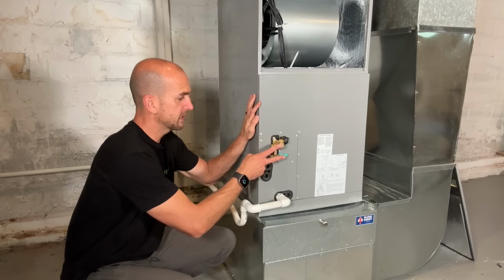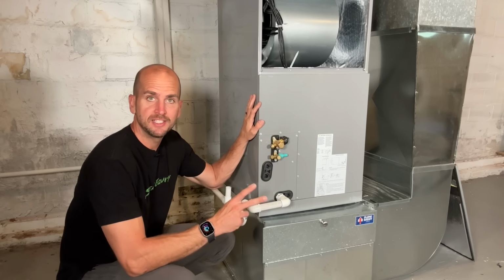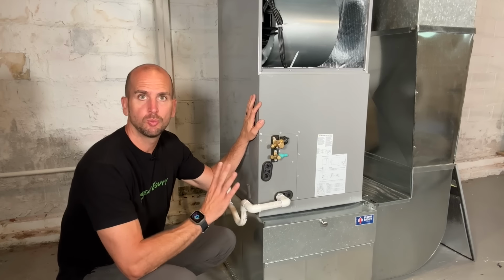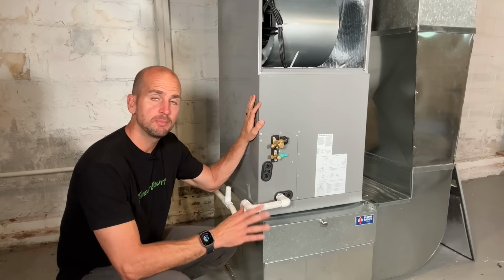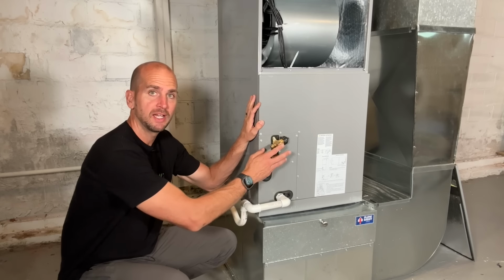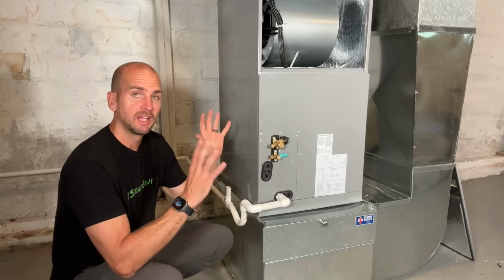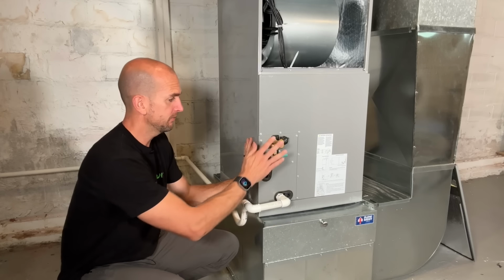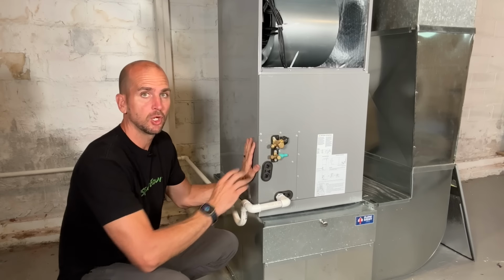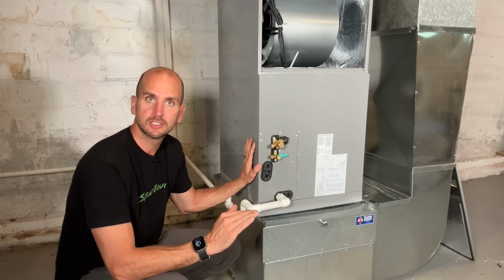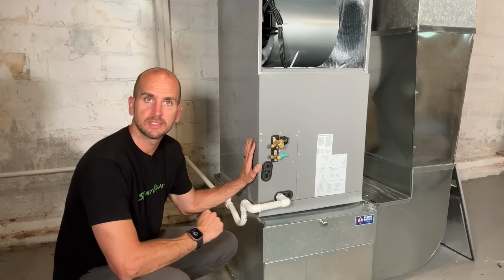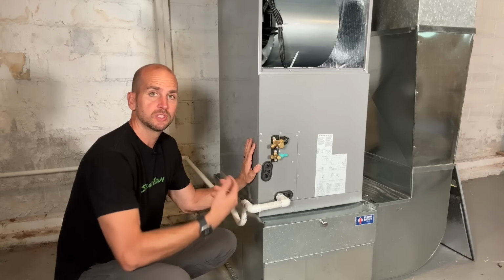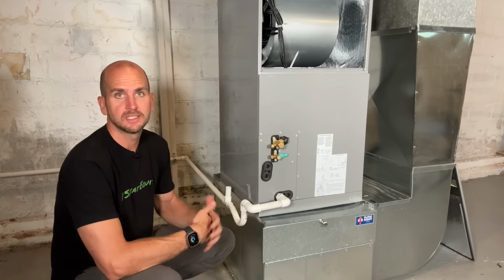So next up, we'll be connecting the No-Vac line set. And this is really the key part to what makes this DIY friendly, because we don't have to install our lines and then pull a vacuum. The line set is all ready to go. If you connect it correctly, you should be able to open up those valves and then everything's gonna work without calling in an HVAC tech. Then when we get that on, we'll just get our thermostat up and running and start testing out the system.